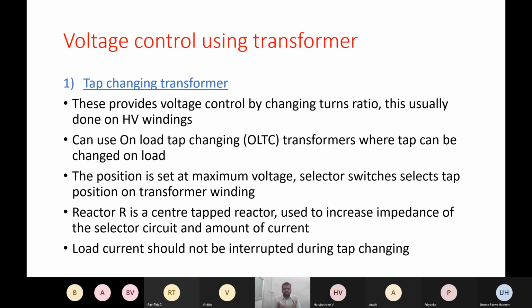So we can use the on-load tap changing transformers, where the tap can be changed on-load. On-load tap changing means we are changing the taps while considering the load. The load will be at the LV winding. Here the position is set at maximum voltage, and the selector switches select the tap position on the transformer winding. So normally the voltage will be kept at maximum, and each selector switch I will explain.